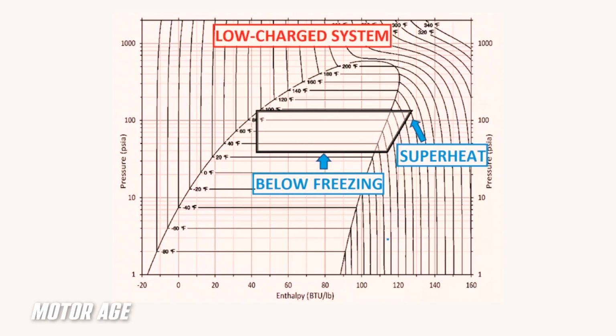So again, the significance of what's drawn against the bell curve here for a low charge is that there's a significant increase in superheat. In other words, outside of the bell curve to the right, it sticks out really far. And the evaporator line that we see here, the temperature across the evaporator is really, really low. It's below freezing, and we have poor system performance. So these are good indicators that the system requires a charge.